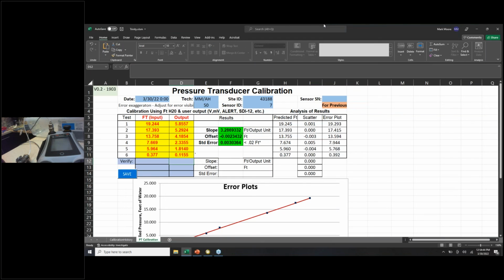All right, I'm going to move this to full screen so you can see this. This is just an Excel sheet that does the math for us. So it takes our input, which was the readings off of our calibrator. Screen went dim, let me bring that up. It takes the input, which was the readings off our calibrator, takes the output, which is what the PT was putting out, and it gives us our slope, offset, and standard error.